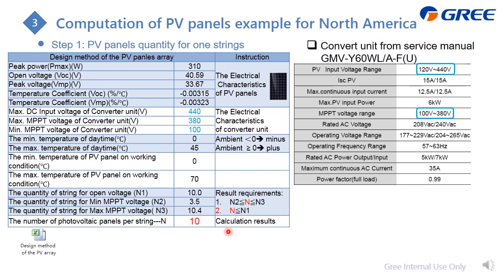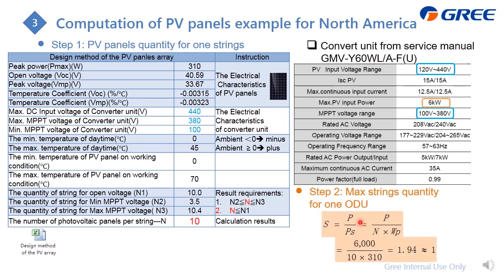And then the next step is how many strings for this outdoor unit, right? So also from this formula, this P is this one, the max PV input power. From this one it is 6. So you put it into this formula, you can get this result: this is only one string, and one string is 10 pieces of the PV panels.